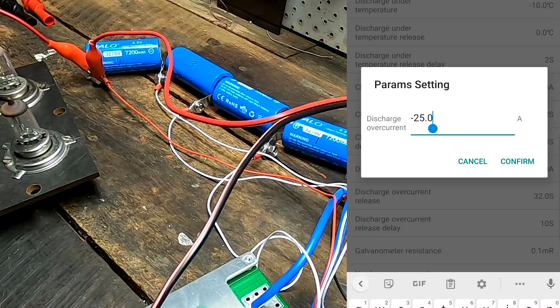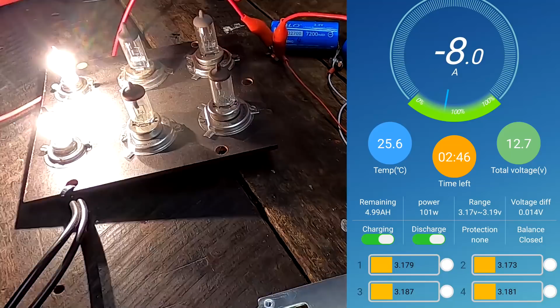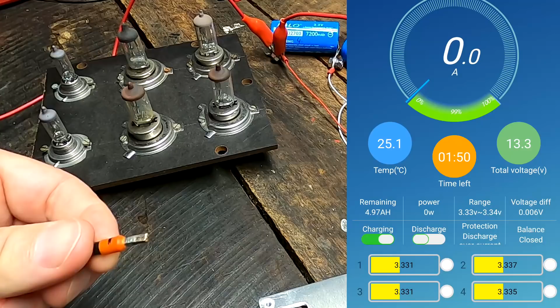Okay, 8 amps, we are discharging. There could be the 10-second delay now. Yep, turns off, bang. Now I think it takes another 32 seconds until it tries again to see if the load is still so high. I can disconnect the loads now and reconnect the load, and it's not doing anything. You can see the discharge button is actually turned off. Let's see if it turns on after another 15 seconds or so. Yep, there it turns on again.